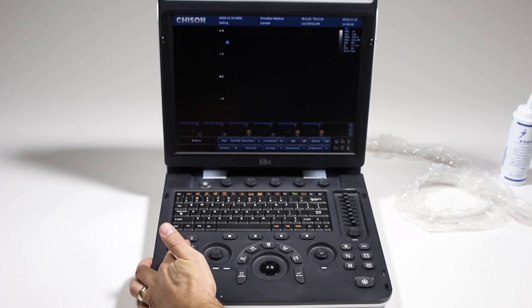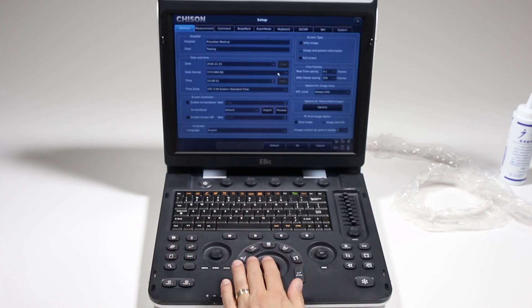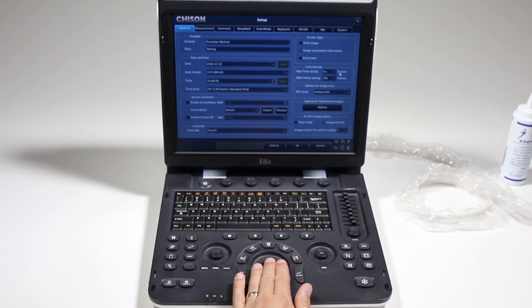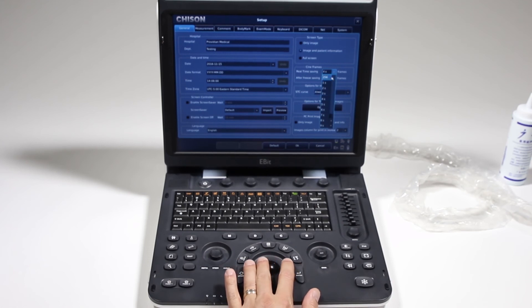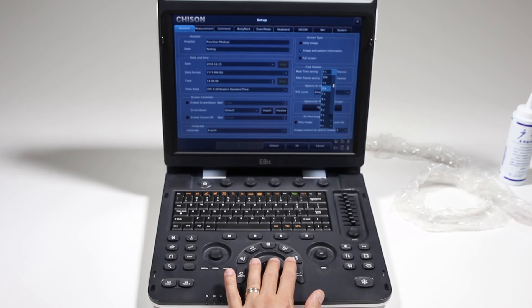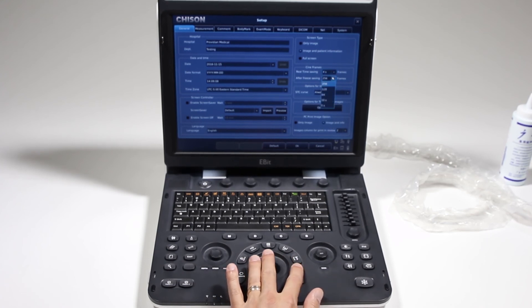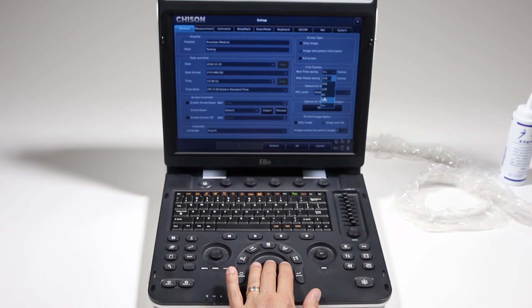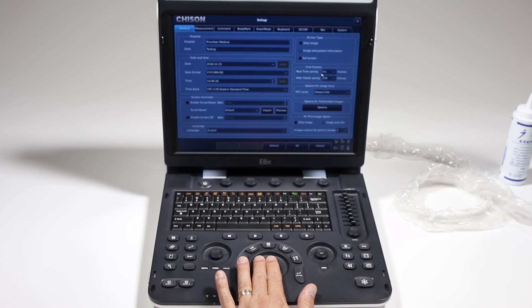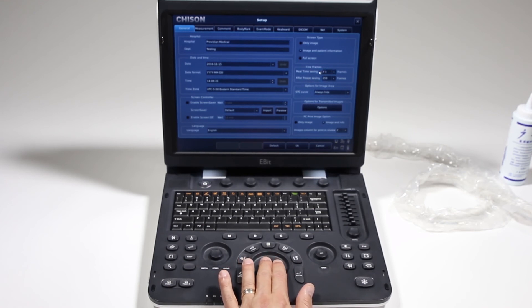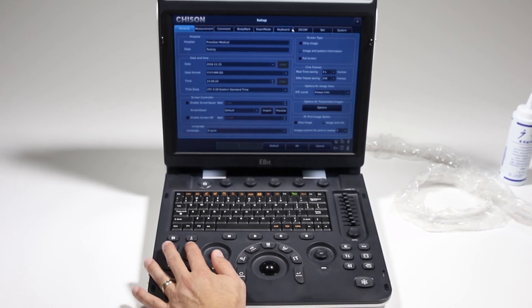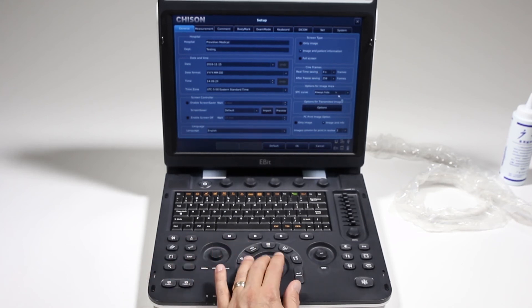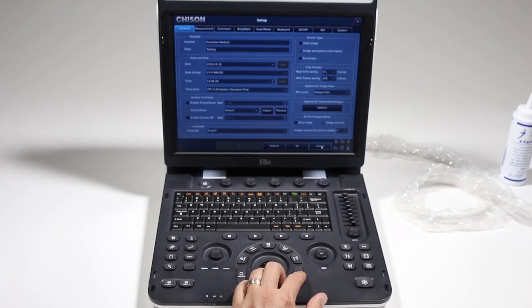I'll show that real quick. You hit this wrench icon and we'll get into depth of these menus later in a different movie. But if I hit this wrench icon, I can save real time saving either seconds or frames. I can save like 256 frames or a number of seconds. And then the same thing here, what do I want to save, the last 10 seconds, 5 seconds or number of frames. This is real time for prospective and retrospective here for after freezing. This is specifically for cine loop review. We'll get into all of these in a later video about the setup, but this is an important thing to note when you're saving images.